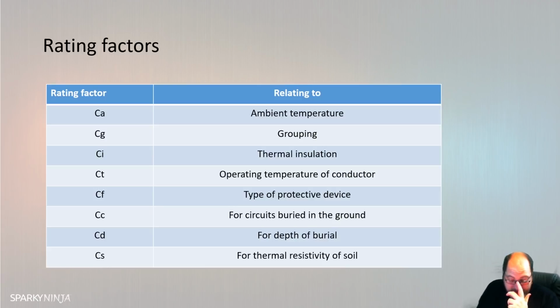We mentioned this coordination thing, and we're going to revisit it right now. If you look at 433.1.1, you'll see it there. The operating current of the protective device shall be not less than the design current, and the rated current carrying capacity of the device, IN, should not be more than IZ. And then in 533.1.202, it says if it's a 3036 fuse, then compliance with the above will be achieved if we have a 0.725 factor. So the type of protective device also needs to be a consideration.